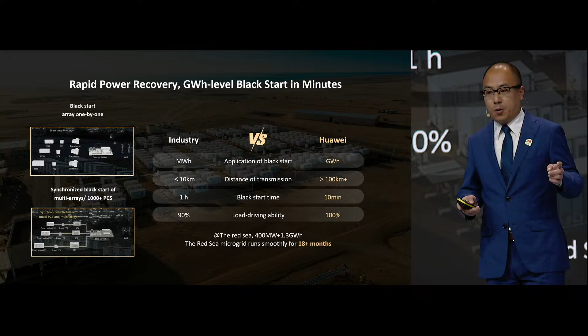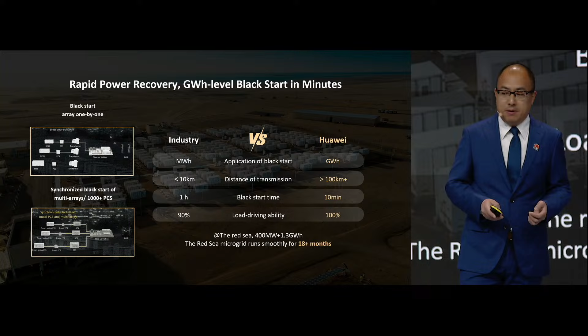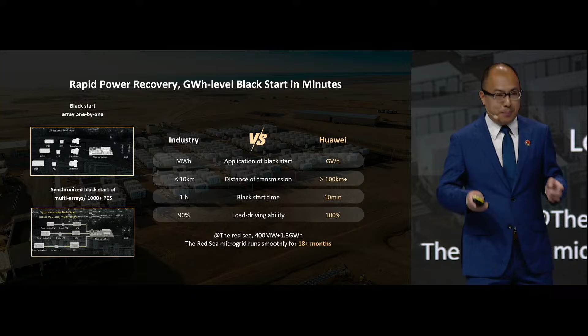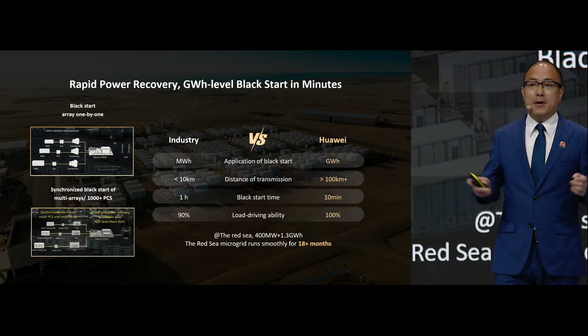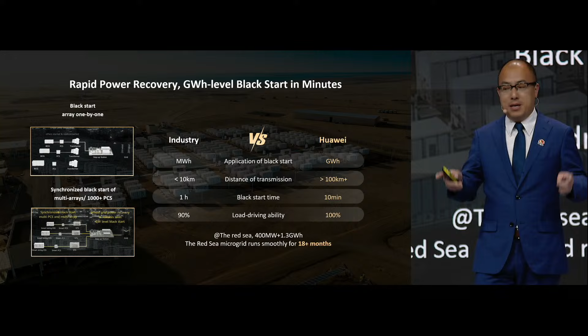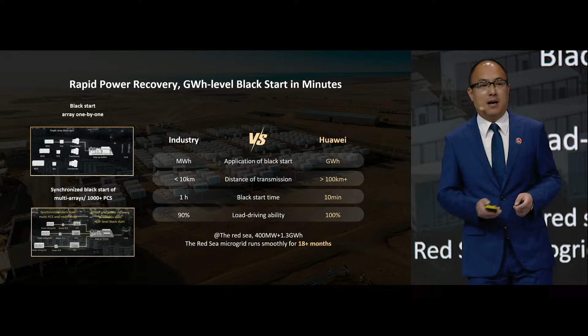Black start is the emergency restart button after grid blackout. In the traditional solution, arrays are black-started one by one. It takes hours or even days to black-start the entire grid, and the process has a bigger failure possibility. Innovatively, Huawei has proposed a synchronized black start technology, which was successfully verified in the Red Sea project. This enables the establishment of voltage across more than 100 kilometers of transmission line, carrying 100% load in just 10 minutes, dramatically reducing the time of black start.